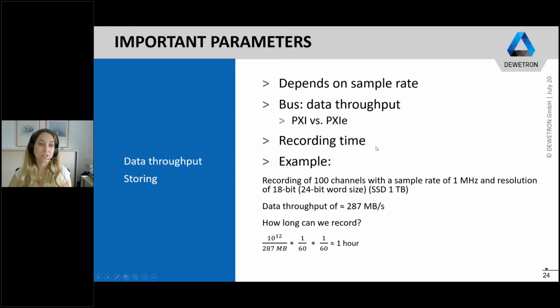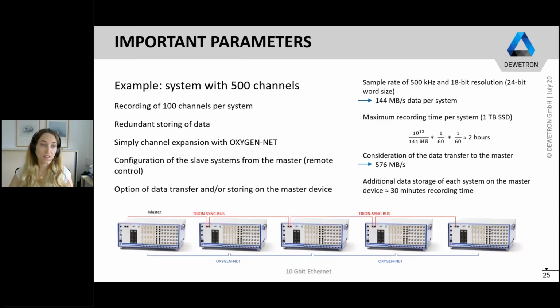Also, the recording time has a lot to do with the data throughput and the storing. If we record 100 channels with a sample rate of 1 megahertz, a resolution of 18 bits and a 24-bit word size, and we have an SSD with 1 terabyte, that comes to a data throughput of 287 megabytes per second. If we record this and store it on the SSD, we can record up to 1 hour until the SSD is full. So if we have high sample rates, the data throughput and the storing should be considered. I have another example here.